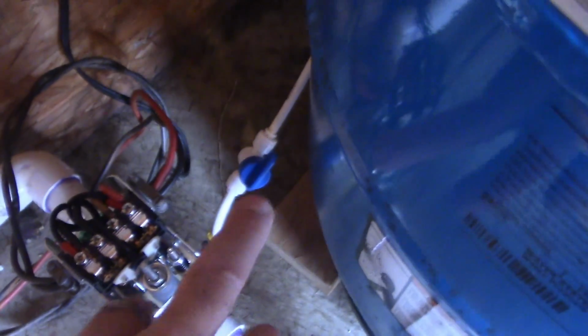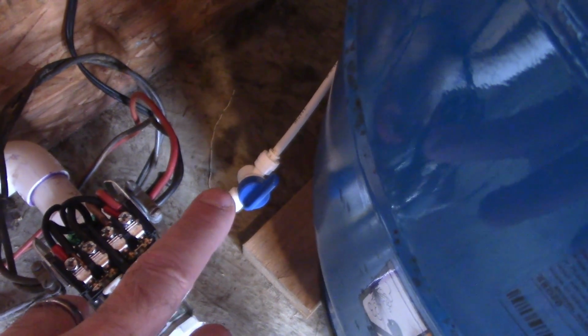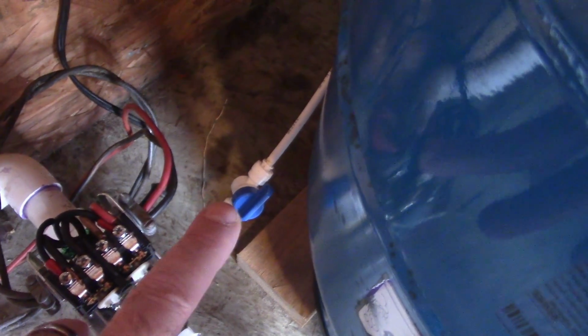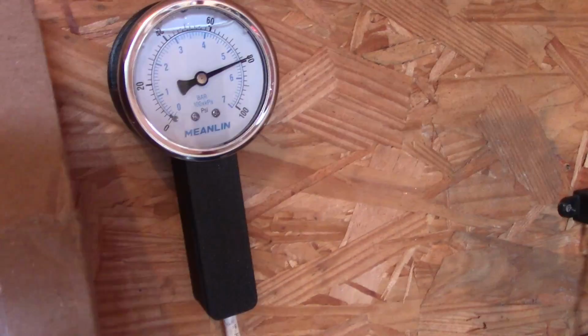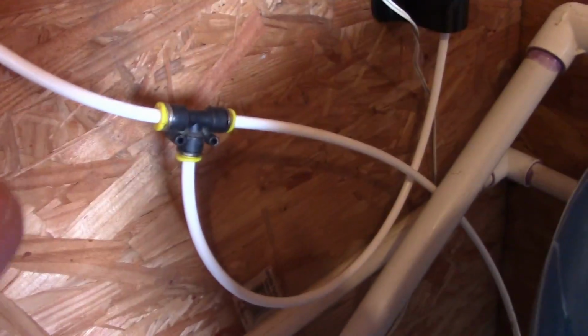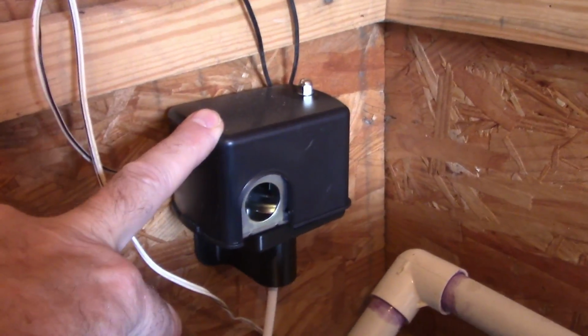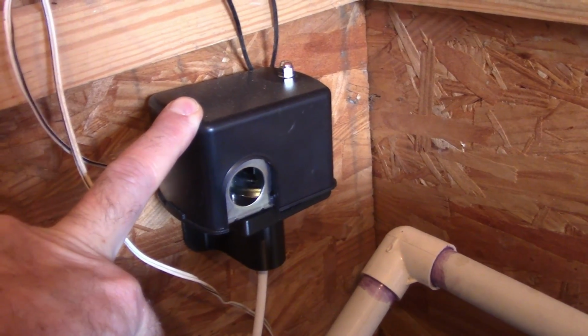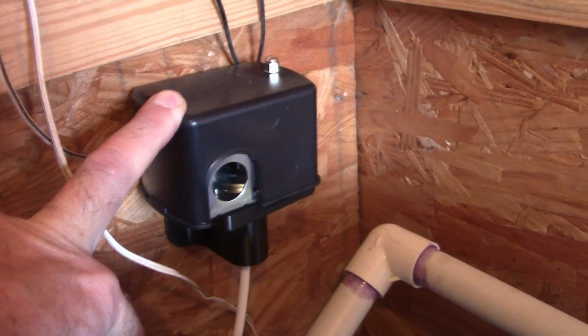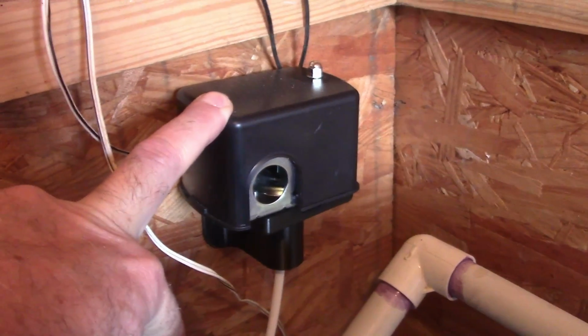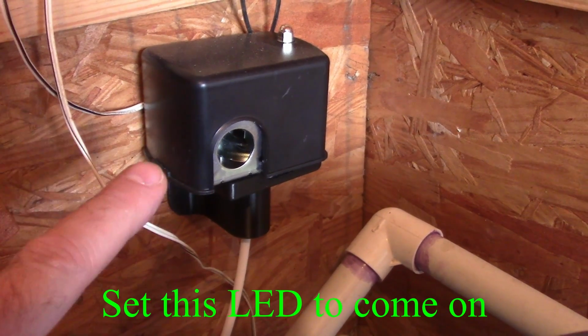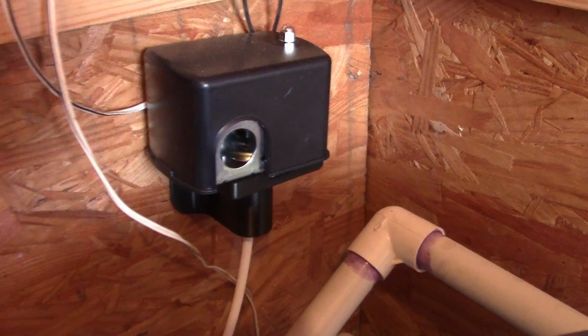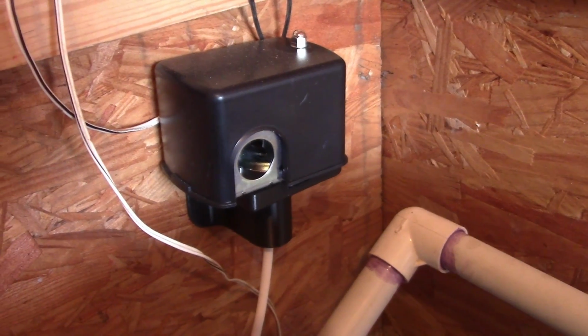Now the other part of this is I have a pressure line coming off the side, and I got that little valve on there in case something past it breaks. I can shut off that water line and keep it from flooding my room in here. But then that pressure line goes up here, it tees off because over here I've got a gauge so I can tell what the pressure is, and then the other side of the T goes over to this, which is just another pump pressure switch. And I use that because you can get these really cheap. They're usually about $20. I'll list one in the description for you. I set this LED to come on below 40 psi. The water pressure gets below 40, because it's normally set at 80. So if it gets down below 40, I've got a problem. There's something wrong with this system.